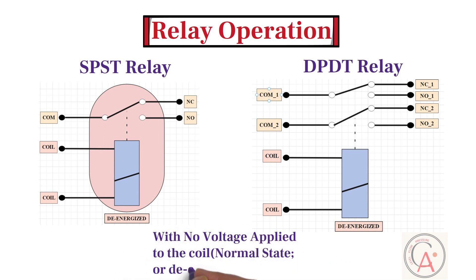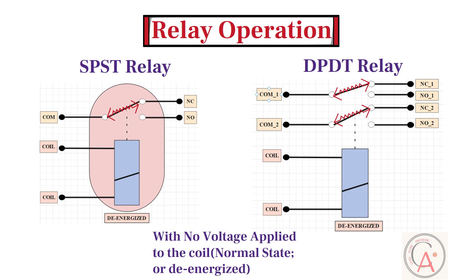In this section, I am going to explain the relay operation of a single-pole single-throw relay and a double-pole double-throw relay. First, let's start with the de-energized state of the relay. As we already know, in a relay, the common contact is attached to the armature and it moves between the output contacts when the armature moves. In the de-energized state, with no voltage applied to the coil, there is continuity between the common and normally closed contacts, and there is no continuity between the common and normally open contacts. This state of the relay is known as the normal state or de-energized state.